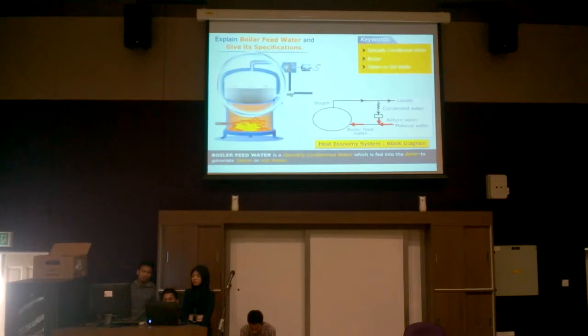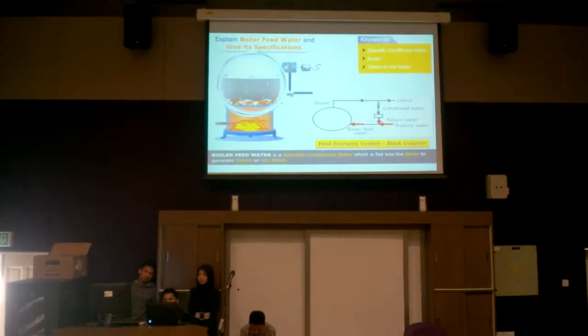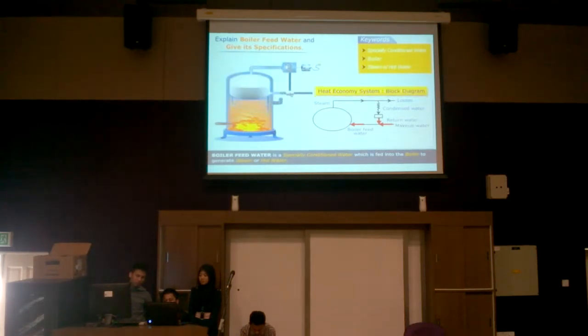Sometimes we see that some impurities settle down at the bottom of the boiler after the steam is produced. We know that steam which escapes from the boiler normally contains liquid droplets and gases. So the remaining water at the bottom of the boiler might pick up all the foreign matter from the water that was converted to steam. This results in the accumulation of impurities at the bottom of the boiler. These impurities can be removed by discharging some water from the boiler to the drain. Such process of blowing the impurities from the boiler to the drain is called blowdown operation.